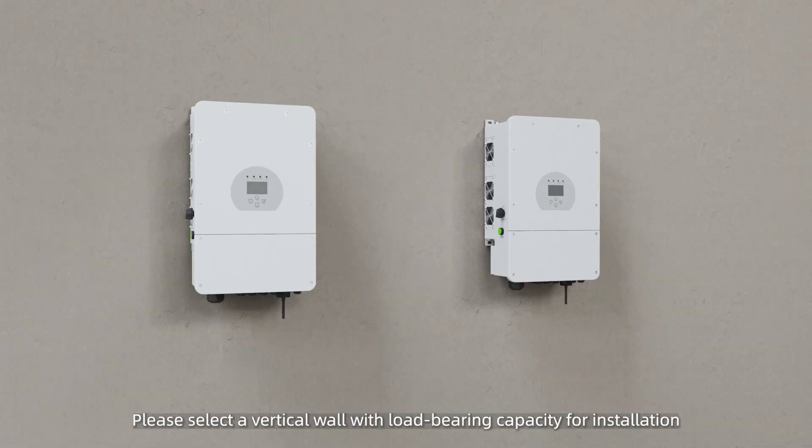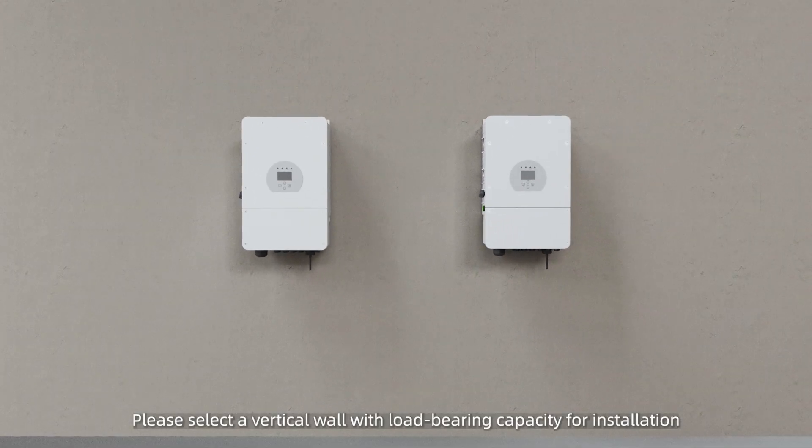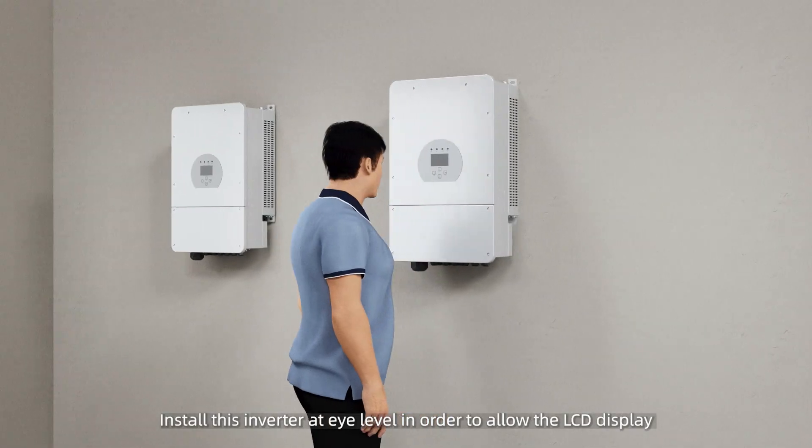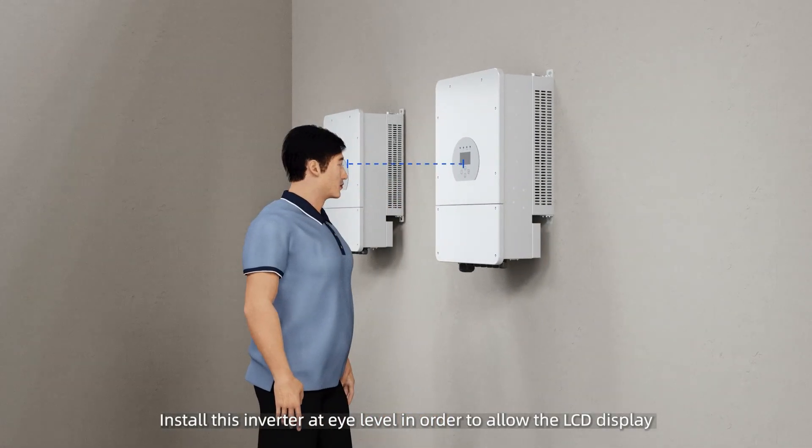Please select a vertical wall with load bearing capacity for installation. Make sure that there is more than 500mm of heat dissipation space around the product. Install this inverter at eye level in order to allow the LCD display to be read at all times.